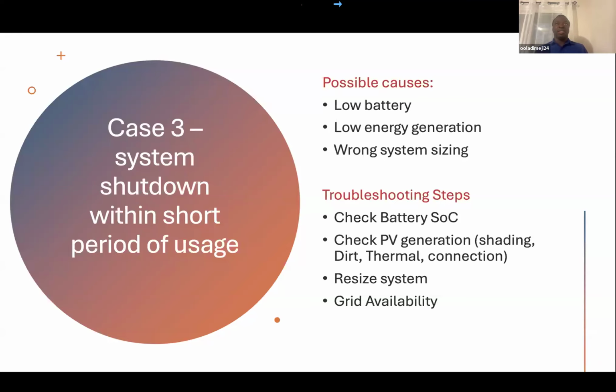Also, you check your PV generation. Is there shading? Is there debris? Is there cloud cover also? Because if your solar is not seeing enough sunlight, then you have low generation at the output. Then thermal: is heat building up within your solar system? Then connections: your MC4 connectors and the cabling down to your combiner box, are they well done? Then confirm the sizing. Is the sizing well done? When you installed the system, is the load connected to the system still as recommended?